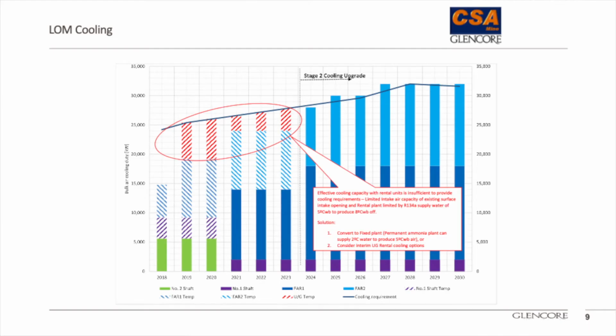As I said, we've got 20 megawatts of chillers today in summer with our 45-degree summer temperatures. Our modelling said we're going to upgrade to 26 megawatts of cooling for this summer and the next 2 summers, but going forward again, we'll need to upgrade again.